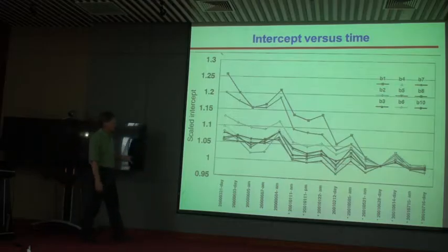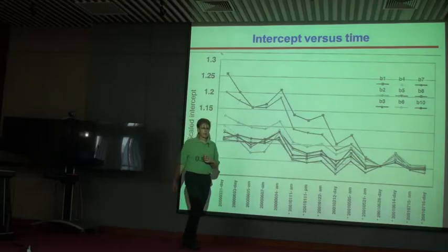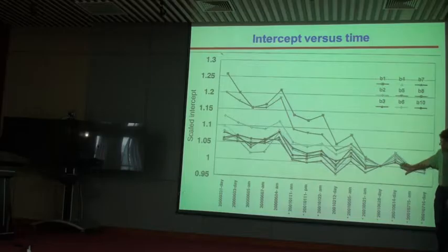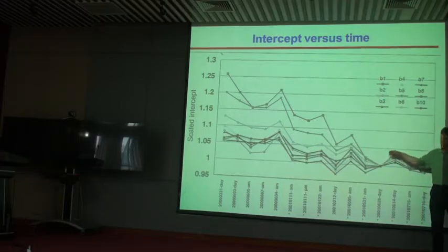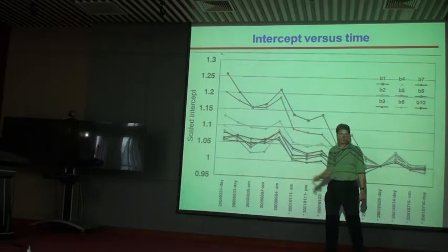And why do we try and do this is, as a function of time, instruments change. So it's a weird one to go back. Basically everything's ratioed to this data point right here. And this is, again, multiple bands from the same radiometer. What's happening is the filters in the instrument, we basically are buying the cheapest filters we can. They're off the shelf. They're not designed to last. We're pointing them at the sun, so they're degrading. And so as a function of time, the instrument itself is losing responsivity.